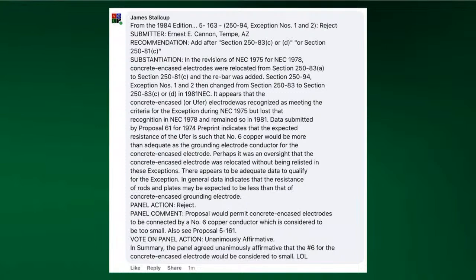Preprint indicates that the expected resistance of the Ufer is such that number 6 copper would be more than adequate as the grounding electrode conductor. Now, this is going back, and they're telling you that they did the testing, the data was submitted in order to say that this number 6 was adequate for this, okay?